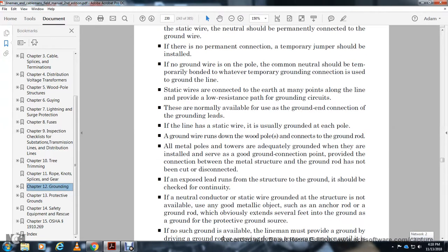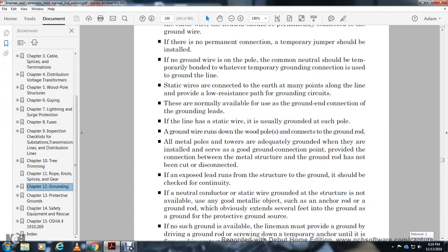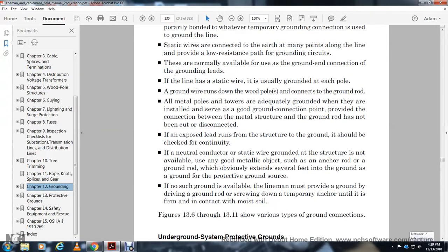Exposed leads or the structure of the ground should be checked for continuity with the neutral conductor and static wire. If a ground structure is not available, any good metal object, such as an anchor rod or ground rod, extended several feet into the ground, can serve as the ground source. If no such ground is available, the lineman must provide one by driving a ground rod or screwing down a temporary anchor until it is firm in contact with moist soil. Figures 13.6 through 13.11 show the various types of ground connections.